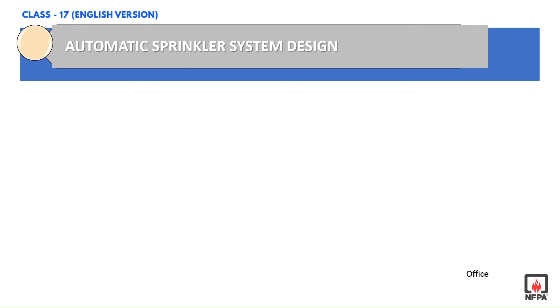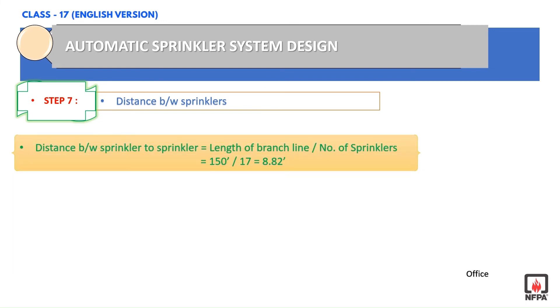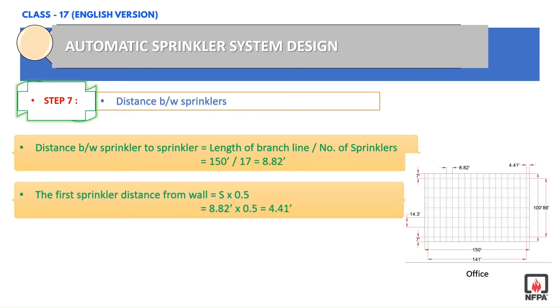Step 7: From Step 6, we already calculated 17 sprinklers per branch line. Now we calculate the distance between sprinklers by dividing the length of the branch line by the number of sprinklers — that is 150 feet divided by 17 — which equals 8.82 feet. The first sprinkler distance from the wall is the distance between sprinklers multiplied by 0.5, giving approximately 4.41 feet. Based on this information, the sprinklers will be placed as shown on the next slide.